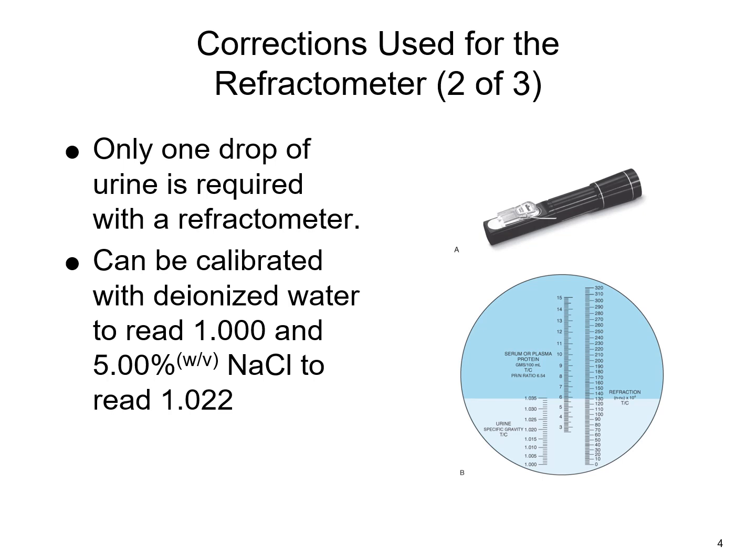Now, if you were to actually have a refractometer and do the calibration process, let's just say you have a scenario where you put the deionized water on there, looking to do your calibration and for it to read at 1.00, but instead it reads at 1.002.